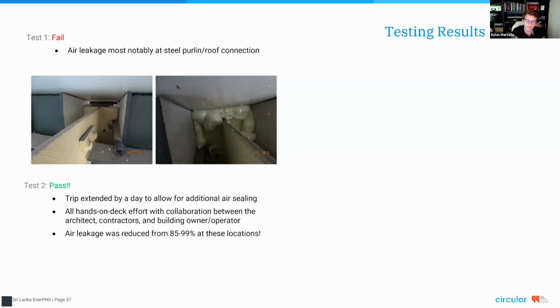We addressed them. On the left you see the condition before we sealed it, and on the right is the sealed condition. In this case, they used spray foam to seal the location, reducing air leakage by anywhere from 85 to 99% at these spots—it smashed that air leakage away.